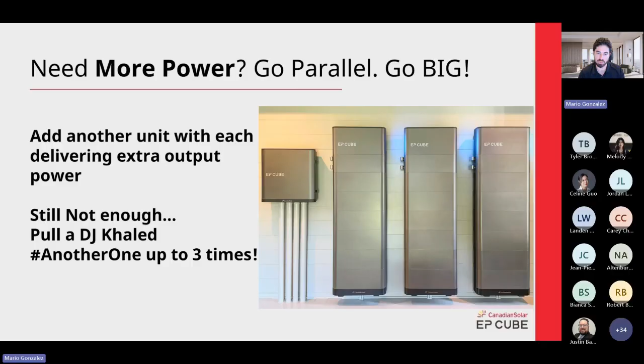EP Cube has 3 operation modes: time of use, backup, and self-consumption. Time of use is basically energy arbitrage, right? You want to charge your batteries from the grid when the energy is the least expensive and sell it when the energy is the most expensive. Pretty straightforward. Backup is basically the battery works as your generator. The software is always going to keep the battery charged, and the only way you're going to use the batteries is if you have a power outage.